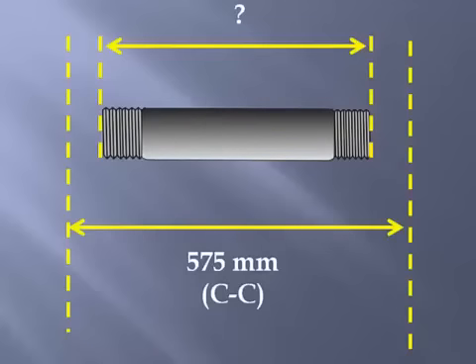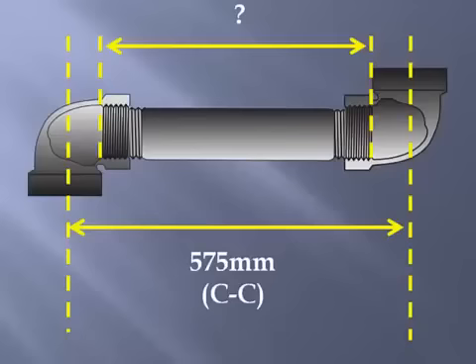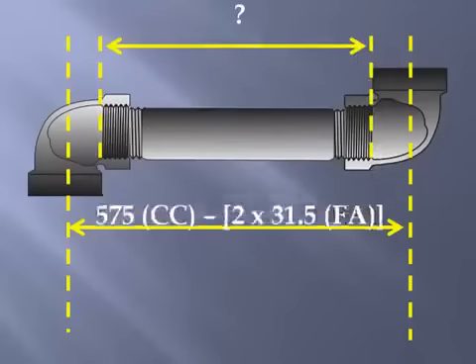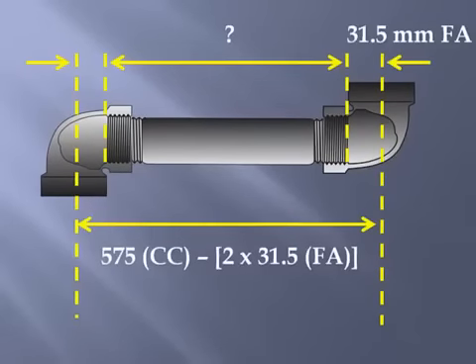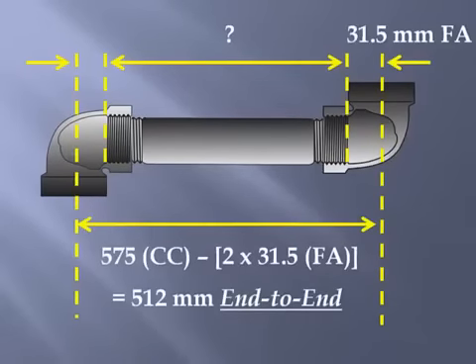Having just calculated for a 31.5 millimeter fitting allowance on 40 mil 90s, that means we'll subtract two fitting allowances from the 575 center-to-center measurement. So 575 millimeters minus 63 millimeters, remember we have a fitting allowance at each fitting, would result in a 512 millimeter end-to-end measurement.